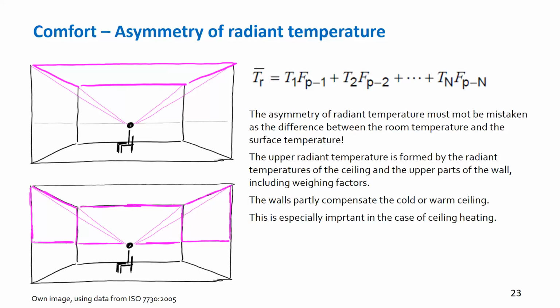And you know, from industry halls, they have these gas radiators, these really hot gas radiators. As long as it's a small spot or like this light, it's weighted with the room angle and gives a nice average radiant temperature. So never be shy about the radiant temperature only of the surface. You always have to weigh it and mix it with the average one.